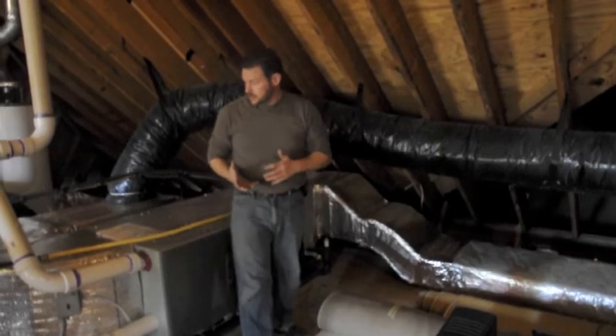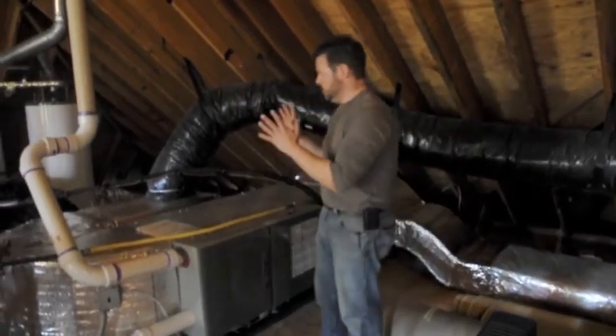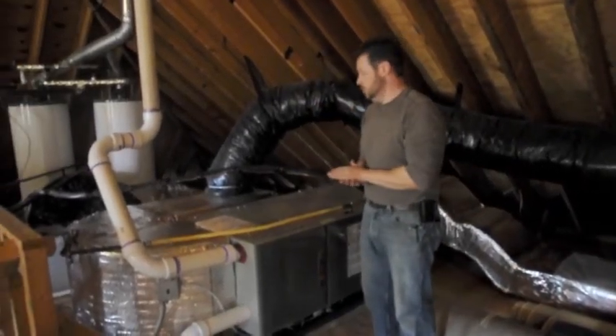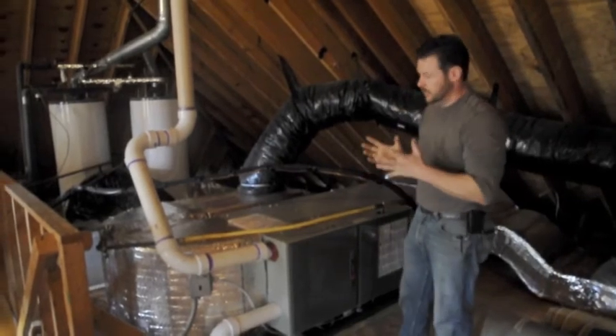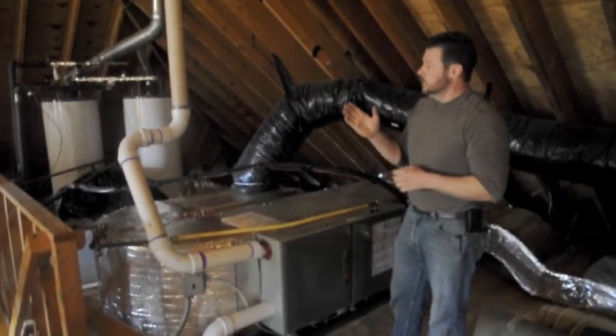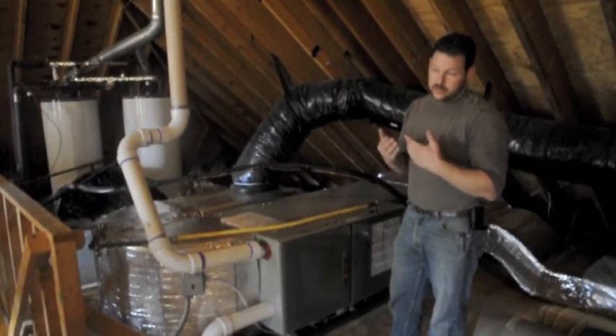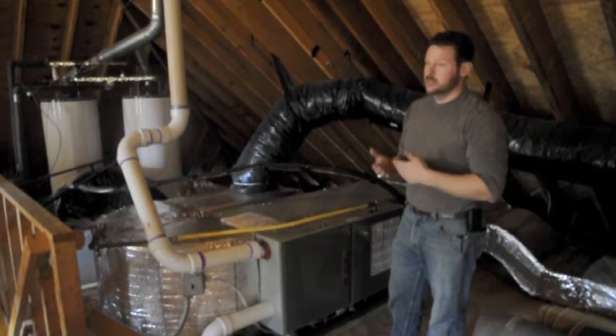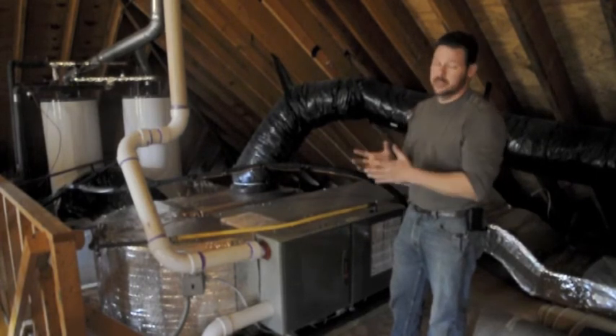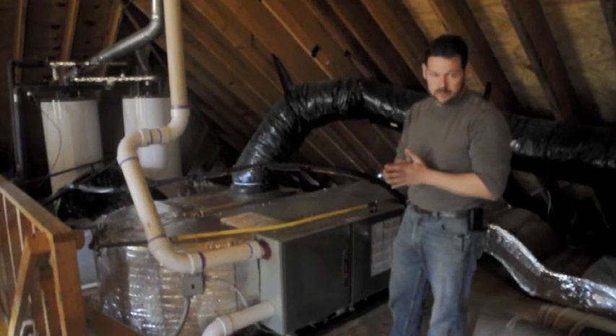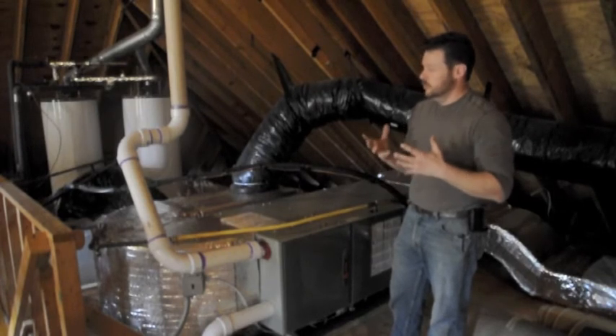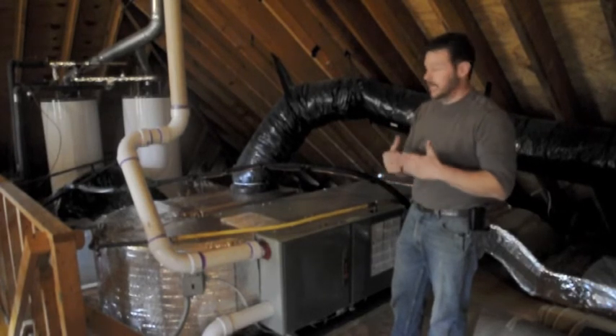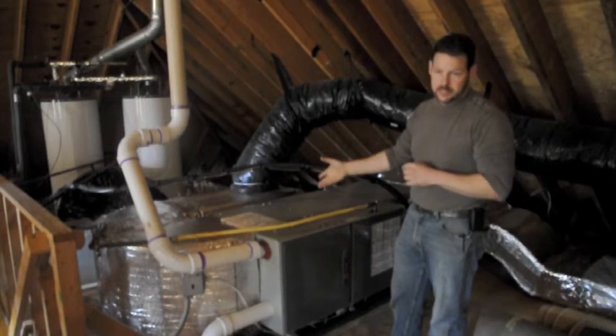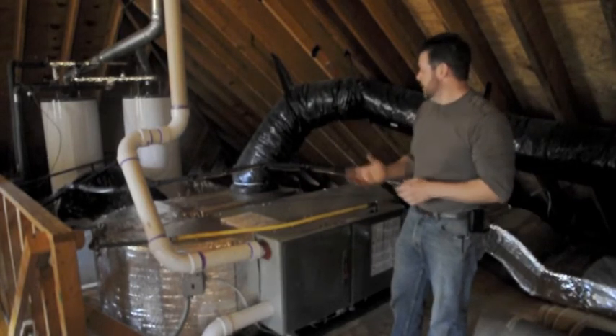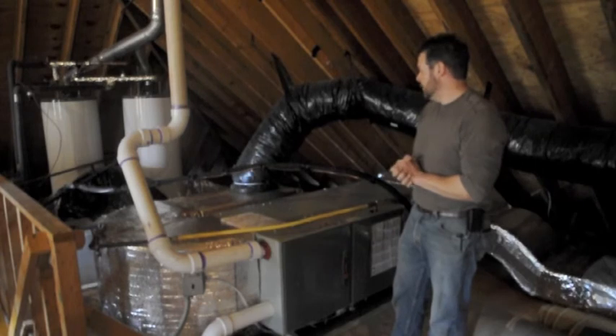The starting point of this job, before we even took out the old system, was to do what's called a heat load calculation, where we will actually come in ahead of time, draw out the floor plan of the house, measure each individual room, the windows, the compass direction of the house, the insulation factors of the house, the insulation factors of the windows, and we're going to come up with airflow per room, which is going to allow us to properly design this system so we know where to put that air. And this is our final product.